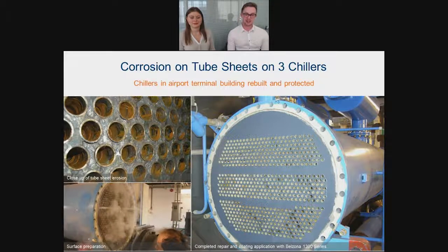The chiller itself was steam cleaned and all those salts removed, and then they followed exactly the same process as you saw in the video a minute ago. They repaired it in 2005, came back and inspected it in 2008 and found it to be in exactly the same condition as it was when the guys reassembled it after they'd coated the system.